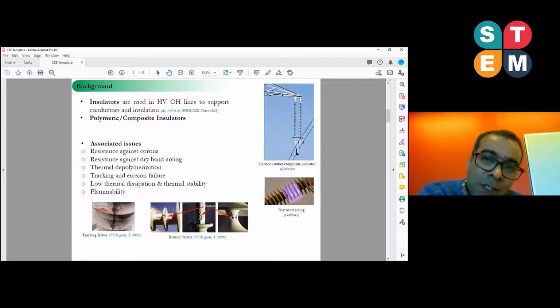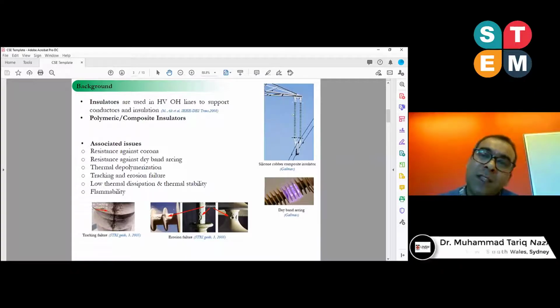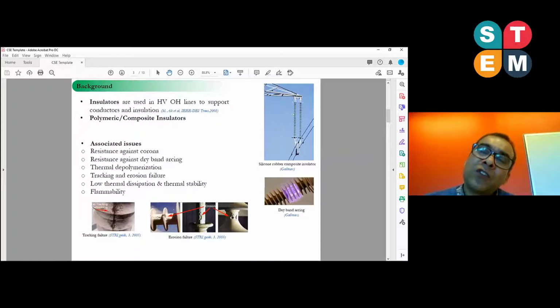The old technology of the insulators is ceramic and glass-based insulators. But in the last 3 decades, there has been a major development in polymeric insulators. Pure polymers couldn't be used for manufacturing insulators because they don't have good mechanical strength. We also need a polymer that is highly hydrophobic and has very good weathering resistance. So we usually add micro or nano inorganic fillers to the pure polymers to get the required properties. That's why we call them composite insulators.